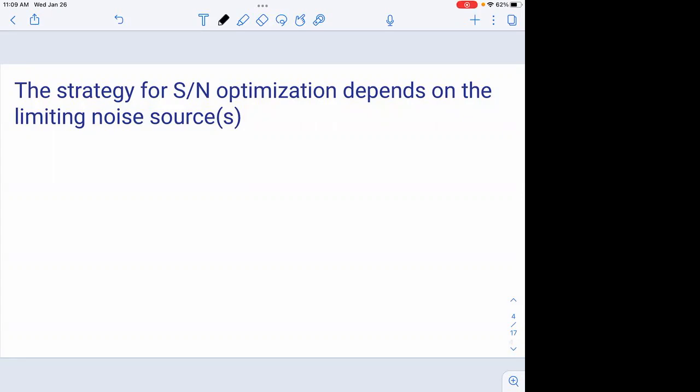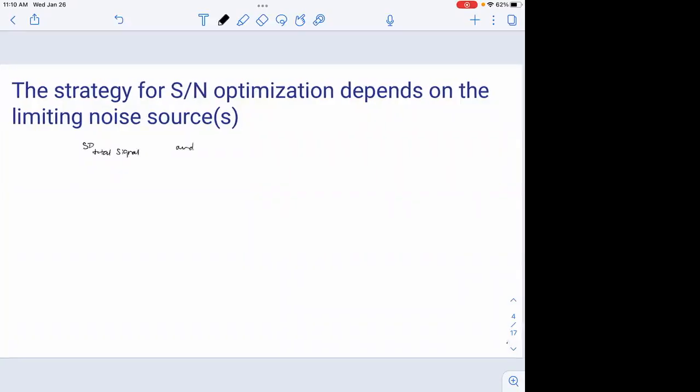So in the lab, if we're troubleshooting, you're going to be able to measure the standard deviation of the total signal. This is like the entire instrument measuring the analyte of interest in a real sample. So that's the standard deviation of that measurement. And you're going to be able to measure the standard deviation of a blank measurement where there's no chemical of interest, right?